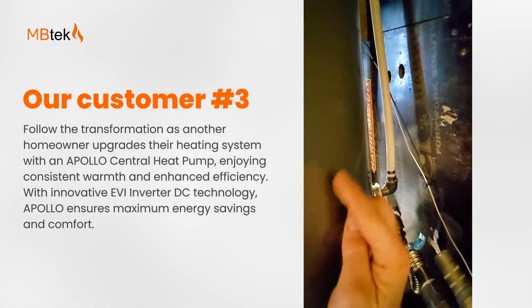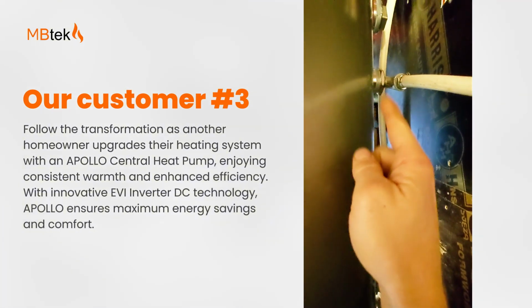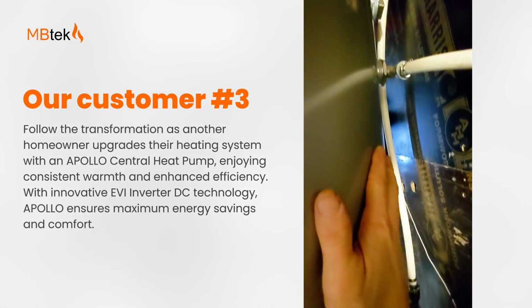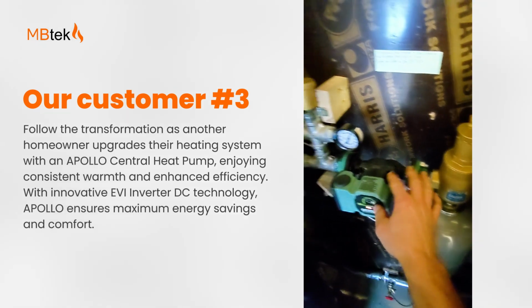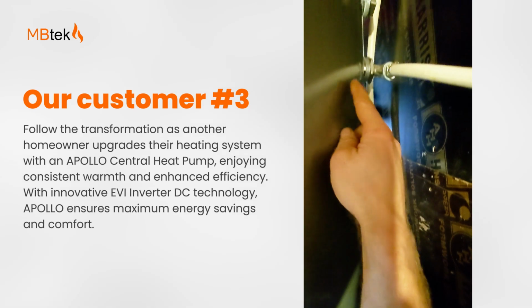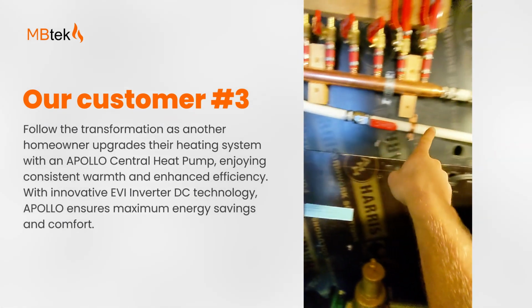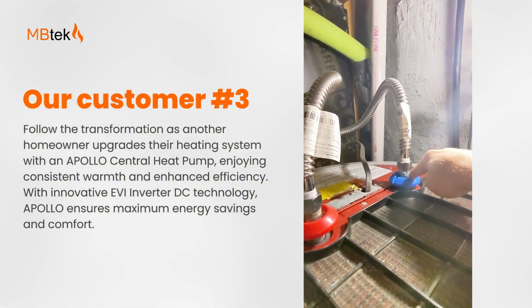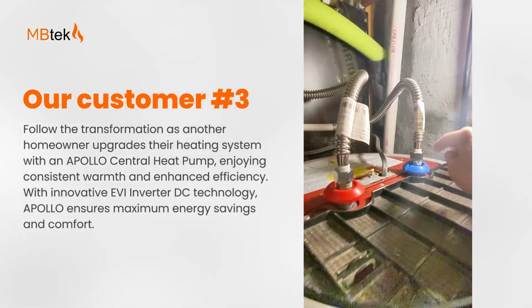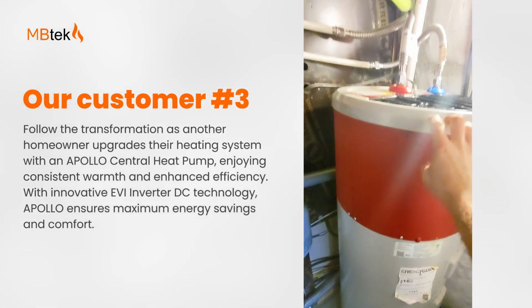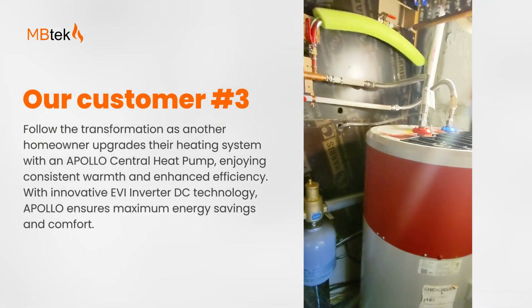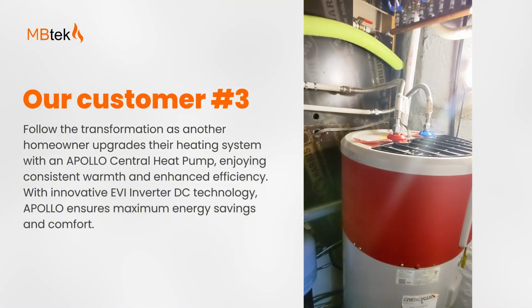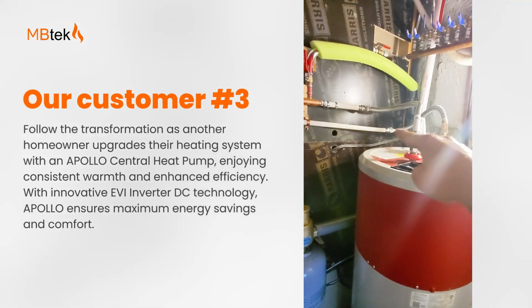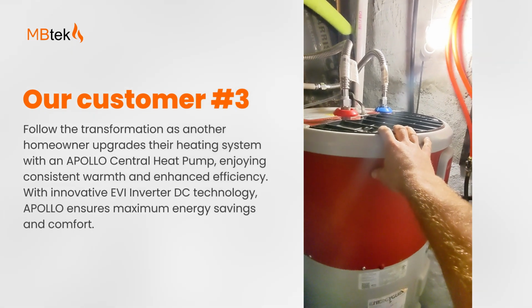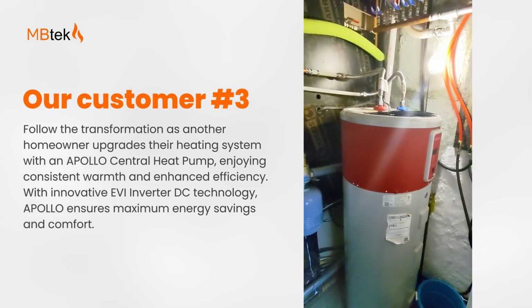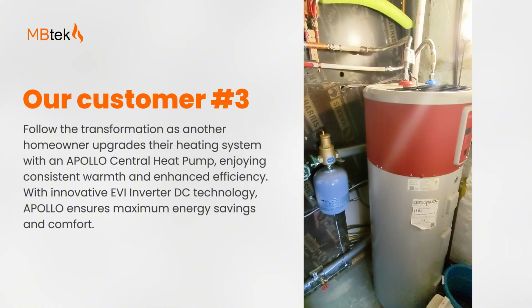So it comes in cold here, runs through the coil, gets heated up by the 130 gallons of water, which in turn are being heated through the heat pump loop, through the heat pump itself. So the water gets preheated, comes back out warm, and goes into the cold water supply line of my domestic water heater, which itself has a heat pump unit on top of it. So if I draw hot water at the sink, shower, whatever, the makeup water isn't even cold. It's already preheated, which means that the heat pump of my domestic water heater is basically not really running ever, or very rarely, just to bring it up to temperature all the way.